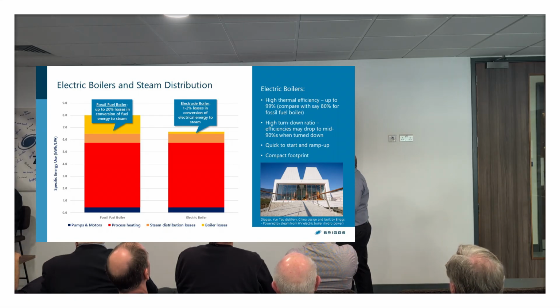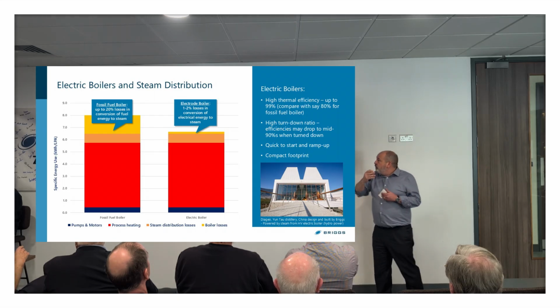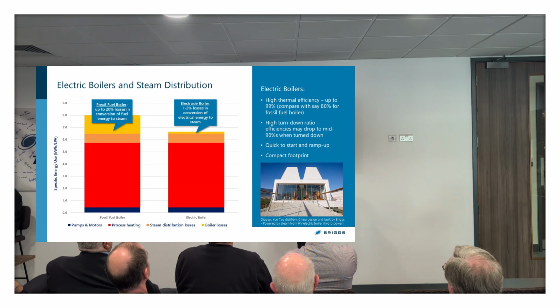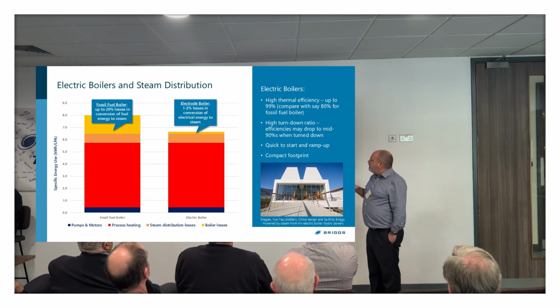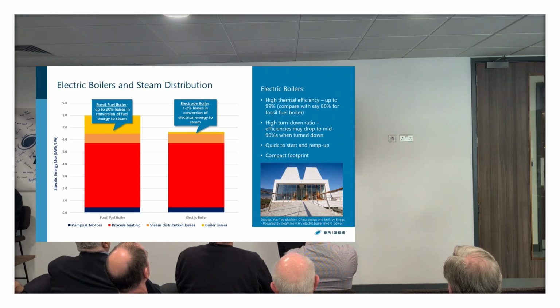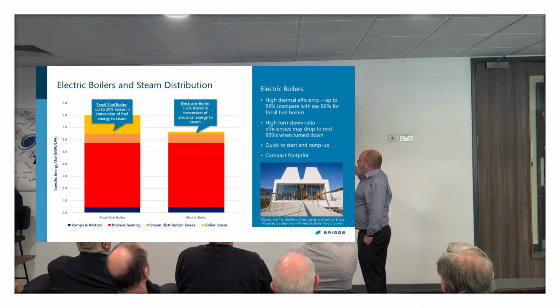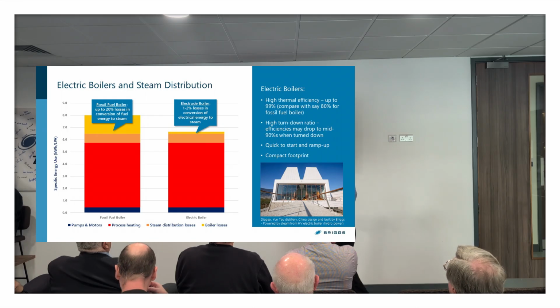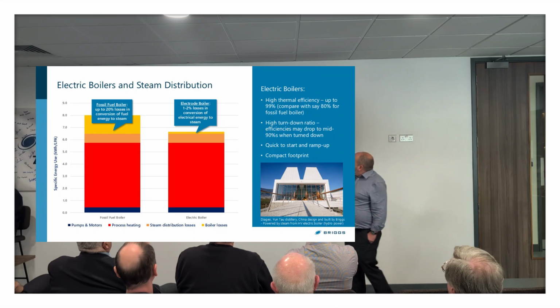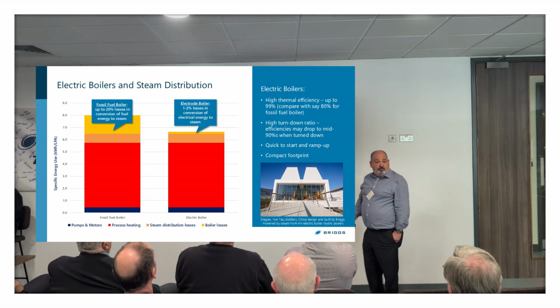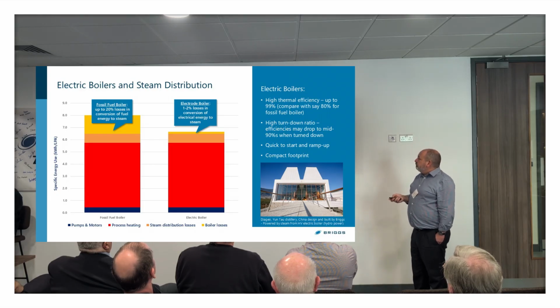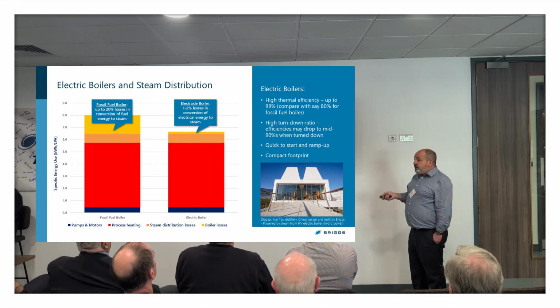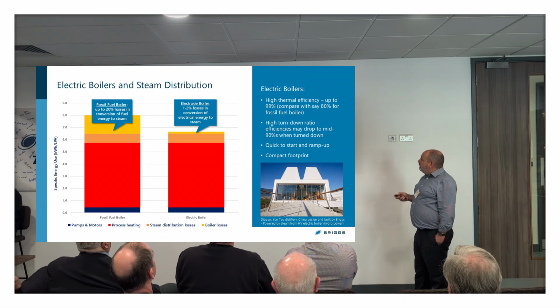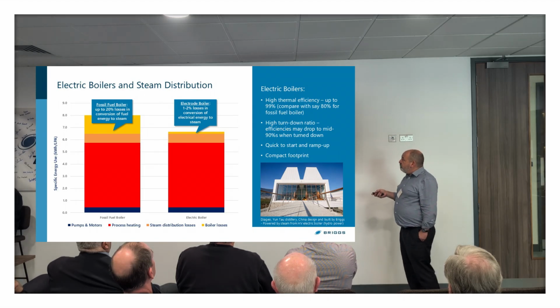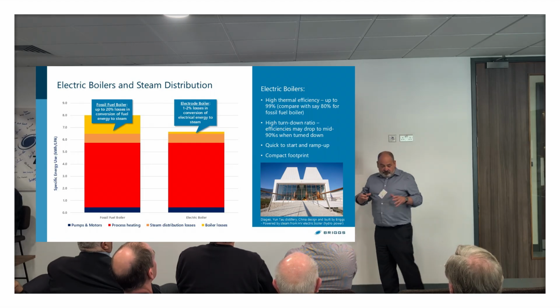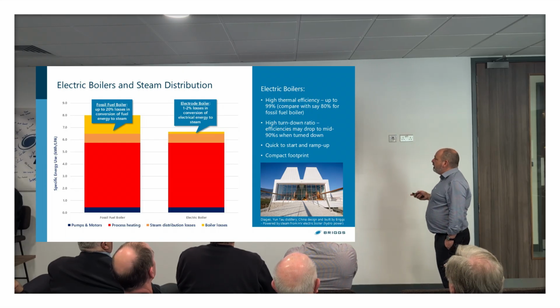So it's worth considering using that technology to make an instant improvement in carbon efficiency and energy use. Here you can see this example is a malt whiskey distillery, with specific energy use of 8 kilowatt hours per litre of pure alcohol, dropping to below 7 just by changing the boiler plant. Electric boilers are really quick to start up and ramp up. They often have a really compact footprint, like a vertical configuration rather than a horizontal configuration, which can have advantages.